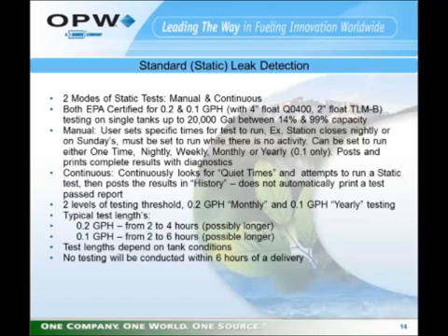If you program a manual test, at the end of the manual test, if the test result is deemed to be a pass, it will print out a report of a passed leak test. If the test result is deemed to be a fail, it will alarm and print out a failed leak test report. If the test is inconclusive, it will print out an inconclusive test result and launch a second test in an attempt to pass.